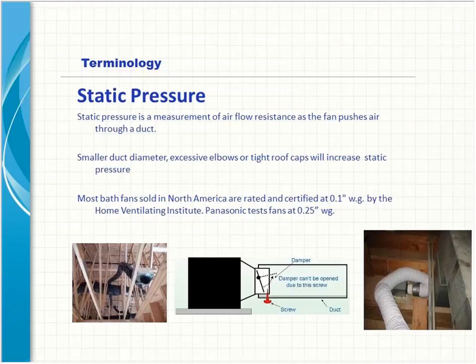And if you've walked through any new construction, you've probably seen some of what's on the screen now. Ductwork draped across trusses. I often refer to what I call the potato chip install, where it dips between each truss, and that has a significant impact on how much resistance there is to the ductwork.